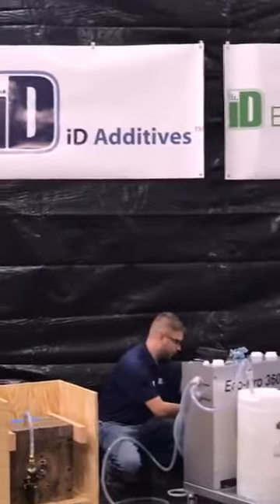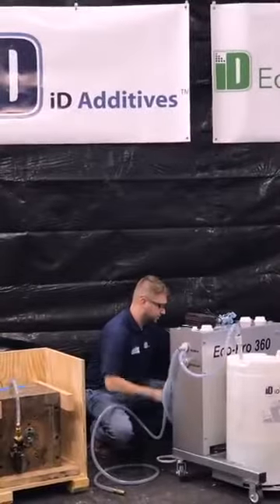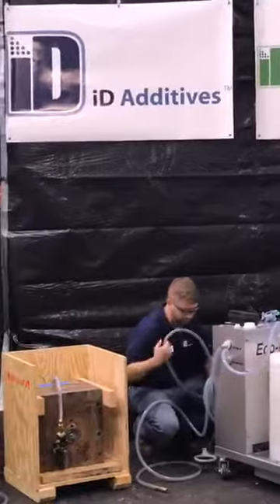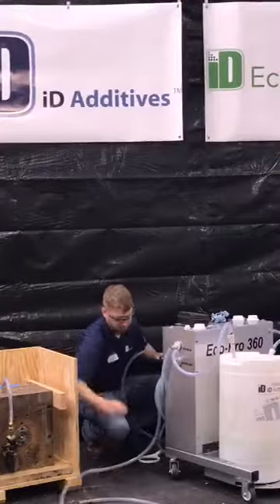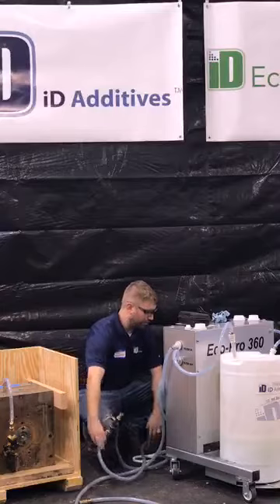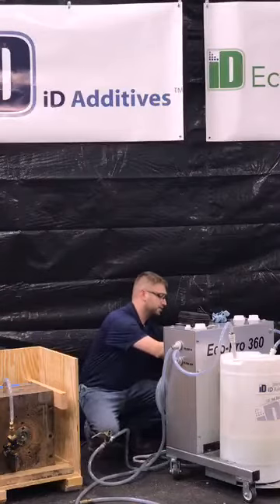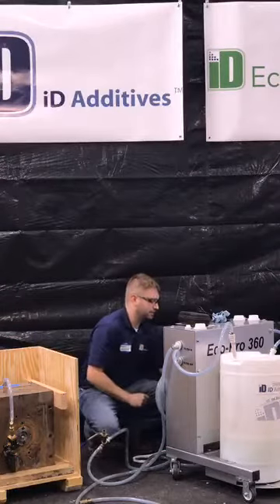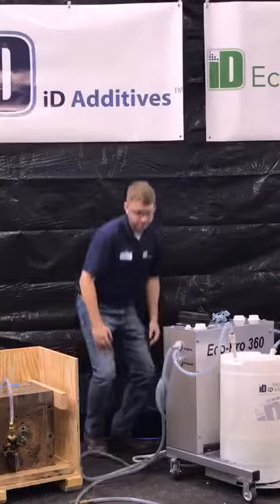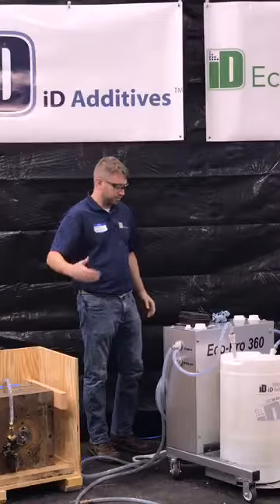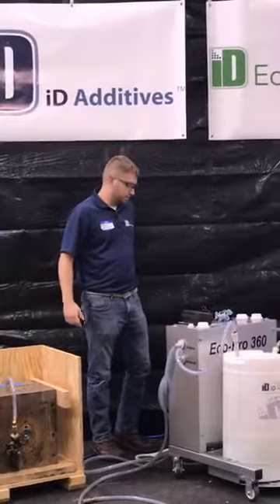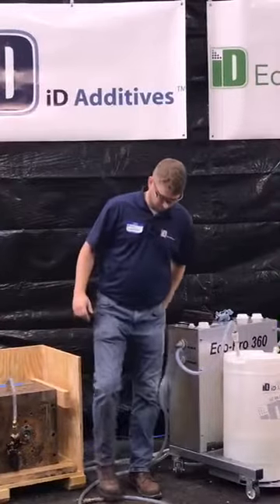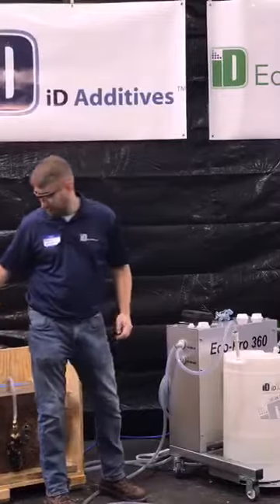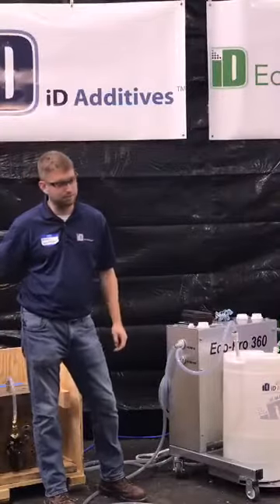Ferrous metal—a lot of passages are made out of steel or aluminum. Your non-ferrous metals, aluminum, brass, tin, all of that, you'll flush with water to neutralize the chemical. If you don't, over time—months—it'll eventually start to break down that alloy, which is why it's important to back flush with water, and why we put the bypass in the filter, because the filter will obviously fill up with chemical. Introducing water dilutes the chemical, breaks it down, and then you can't reuse it.